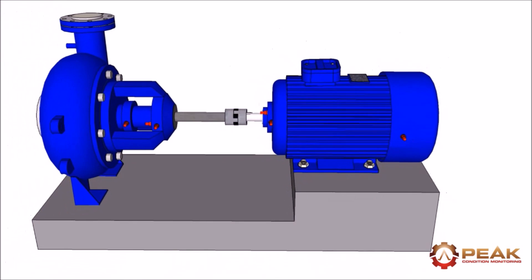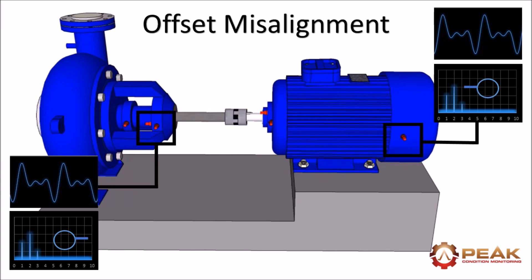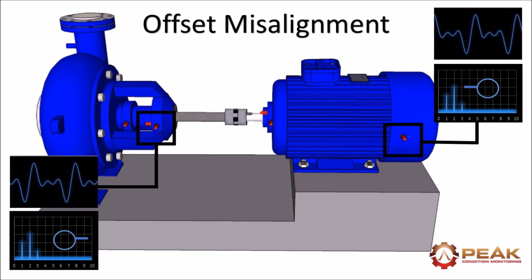Phase data is also critical when confirming offset and angular misalignment in equipment. If offset misalignment is present there will be peaks at 1x, 2x and 3x in the axial direction with the waveforms out of phase.